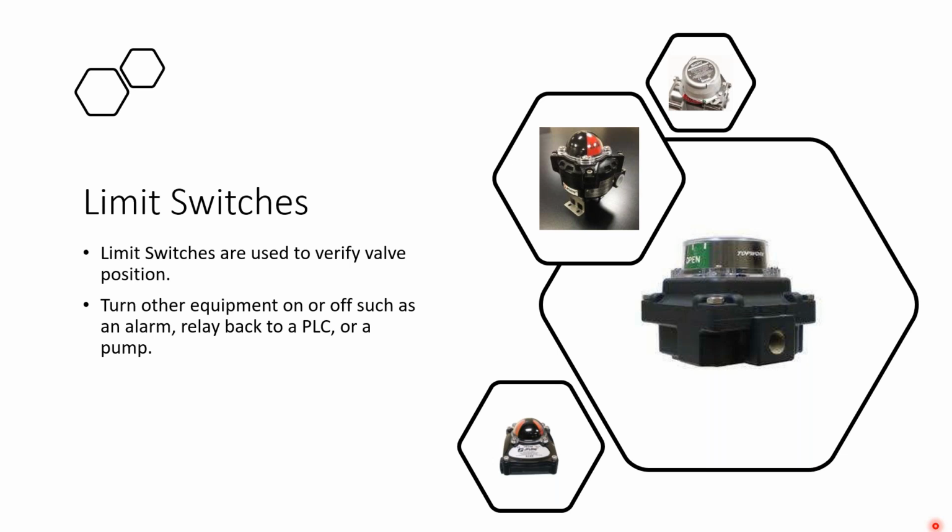Mechanical switches, again, are typically used only where it's safe. We know that it's going to be sealed, we know everything is intact, and it's a good environment where we can safely use a mechanical switch. Whereas with a proximity switch, we have to make sure they do not have any chance of an explosion, a spark, or an arc.